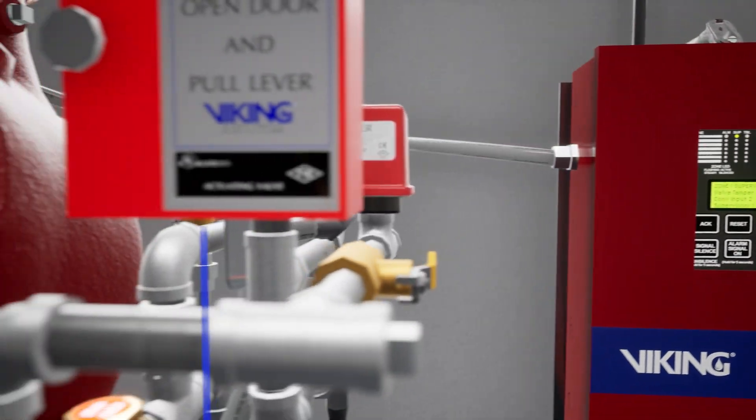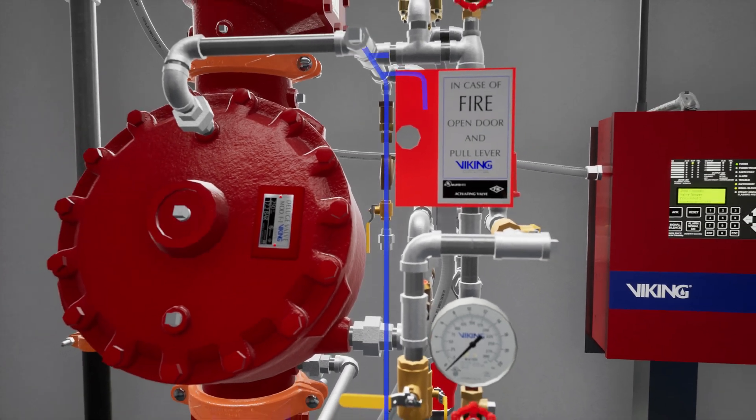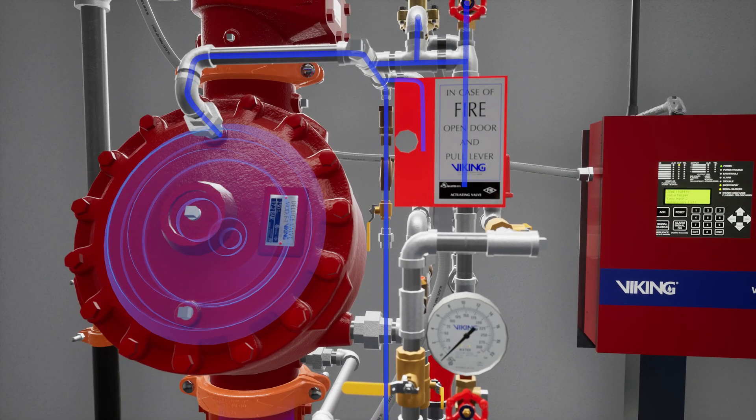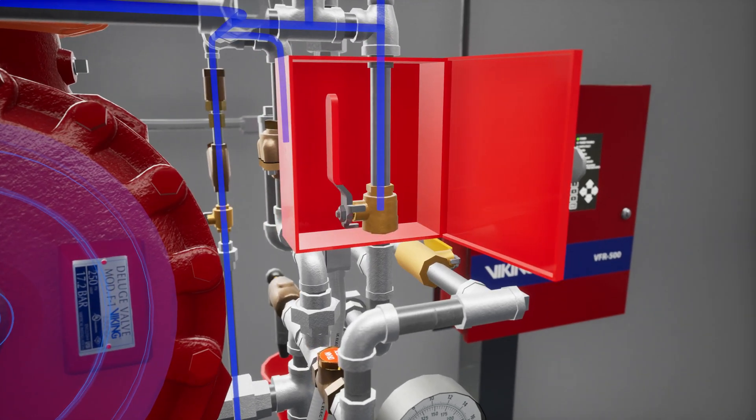Open the priming valve and allow the priming chamber pressure to build. Let's open the emergency release to establish flow through the priming chamber. This will remove any air trapped in the priming chamber.